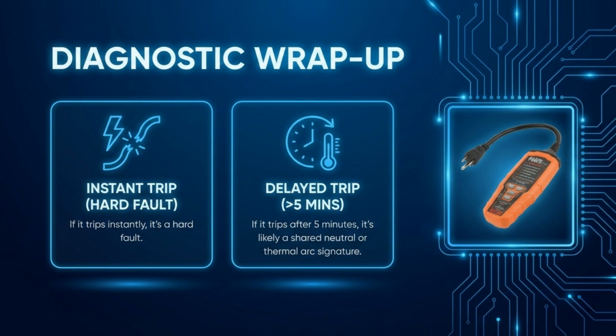In the diagnostic wrap-up, an instant trip usually indicates a hard fault. If the trip is delayed by more than 5 minutes, it is likely a shared neutral or a thermal arc signature.